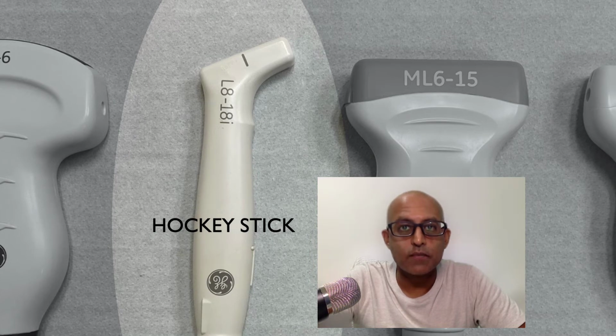Next, we have the hockey stick, which has a frequency range from 8 to 18 MHz. What this means is that it provides high-resolution images, but the penetration is low and can really only be used for superficial structures. Another thing to note about the hockey stick is that it's got a very small footprint, so it's really only useful for scanning focused areas. In musculoskeletal ultrasound, it's typically used for the hand, wrist, maybe the elbow, ankle or foot, and it can be used for scanning the joints, the nerves and tendons in these areas.